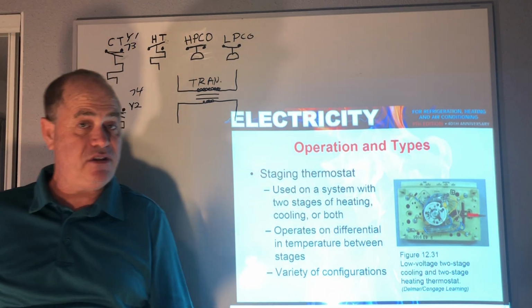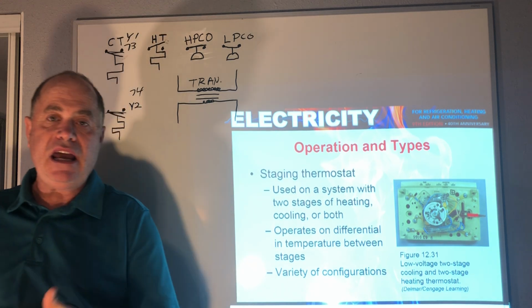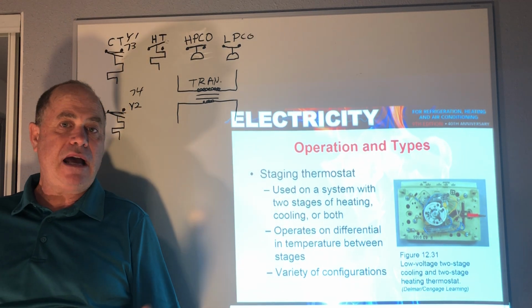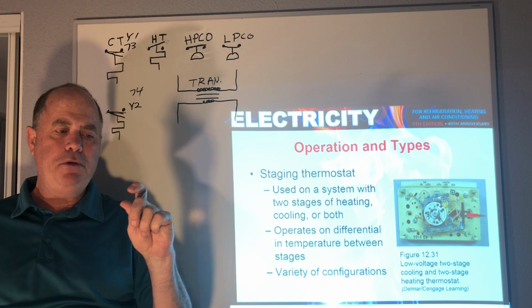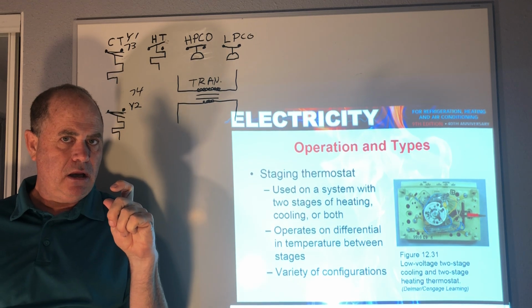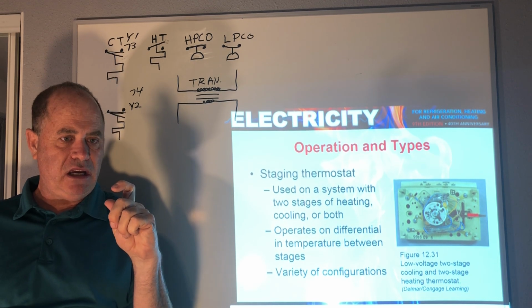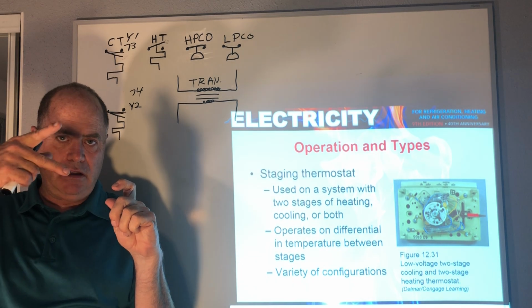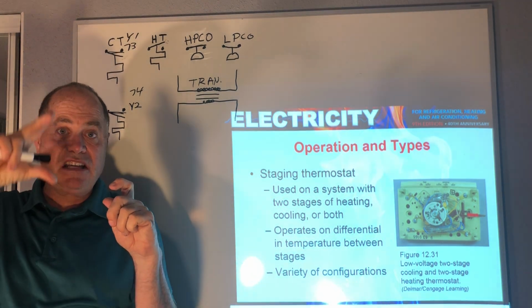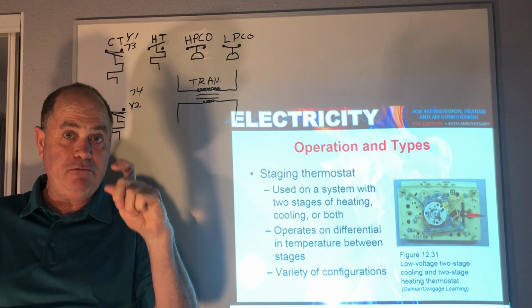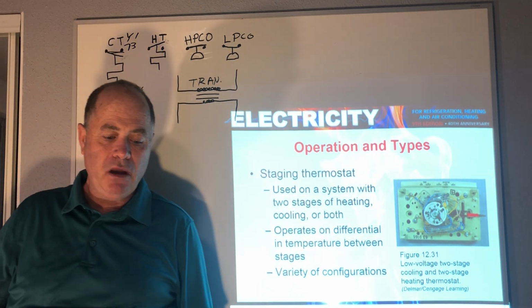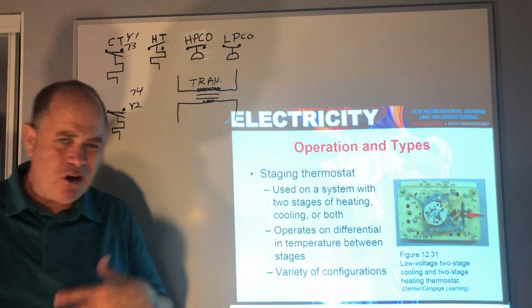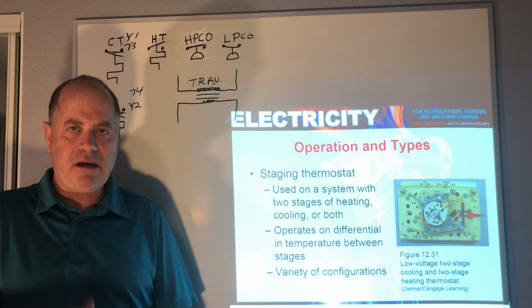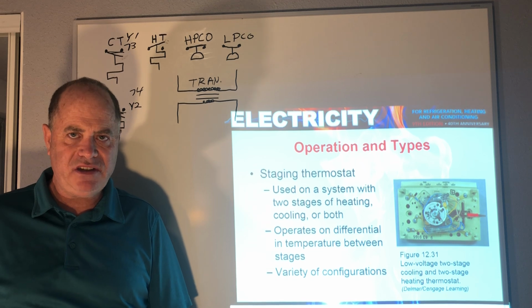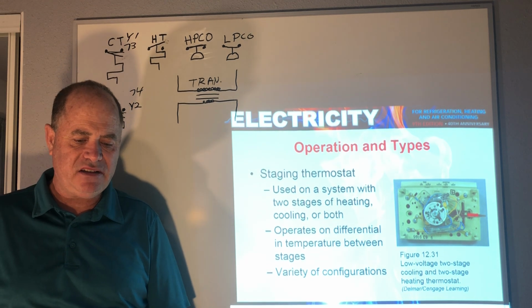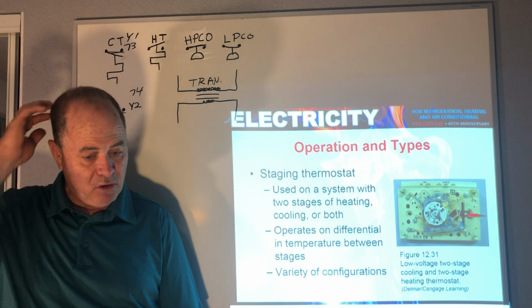And then also we have it similarly for heating, W1 and W2, where actually the flame, the gas valve, will open up partway with W1. And then if you need more heating, the gas valve contact closes for W2, and then the gas valve opens all the way, and the flame, that blue flame, grows a little bit, producing more heat. And there's all kinds of new technology coming out all the time, but I want to give you the basic concepts of how these staging thermostats work. Okay.